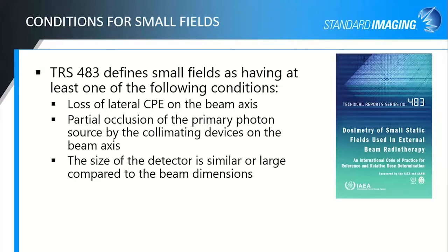Conditions for small fields, I guess, is a good place to start on this. The TRS 483 report, that's a joint small field report from the IAEA and the AAPM, defines small fields as having at least one of these conditions: either loss of lateral charged particle equilibrium on the beam axis, partial occlusion of the primary photon source by the collimating devices on the beam axis again, or that the size of the detector is similar to or large compared to the beam dimensions.